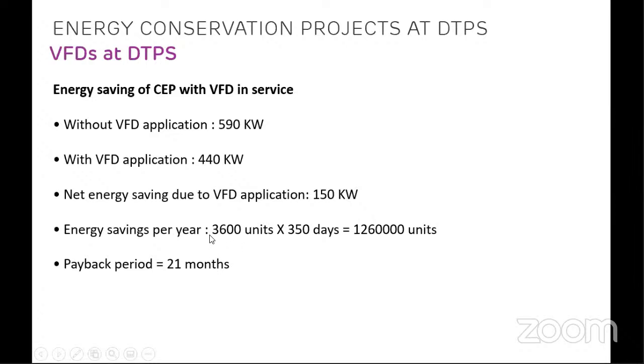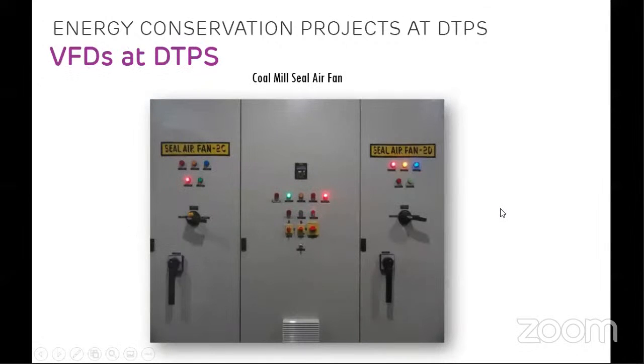If you apply this for 365 days per year, we get 12,60,000 units of saving. And if you apply the cost of the VFD, then the payback period came out to be 21 months. Within 21 months, this VFD has given back its cost, and now it is giving us additional savings. So you can see how a single VFD can give such a large saving of 150 kilowatts continuously. Then in a similar way, we installed a variable frequency drive for the coal mill seal air fan.